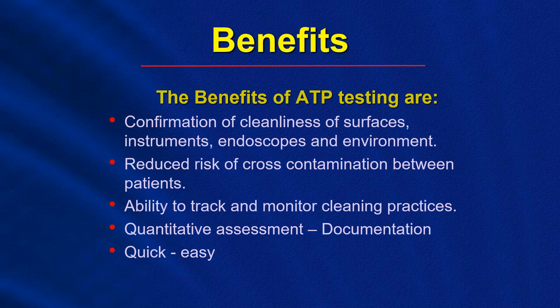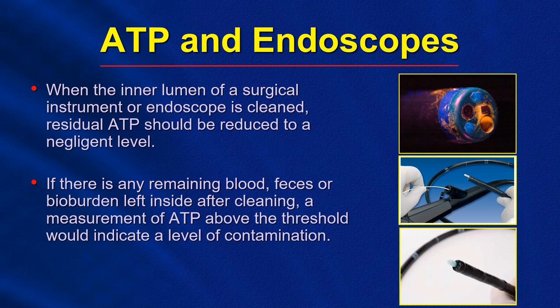So with ATP and endoscopes, just to mention quickly, we touched on GI and endoscopy suites. When the inner lumen of a surgical instrument or endoscope is cleaned, residual ATP should be reduced to a negligible level. If there's any remaining blood, feces, or bioburden left inside after cleaning, a measurement of ATP above the threshold would indicate a level of contamination. Now, this photo here shows on the right-hand side top picture, that's residual bioburden seen under special fluorescent lighting, which may not normally be seen by the naked eye. Surfaces and inner lumens that test higher than acceptable will again need to be re-cleaned and retested before sending for final sterilization or high-level disinfection.